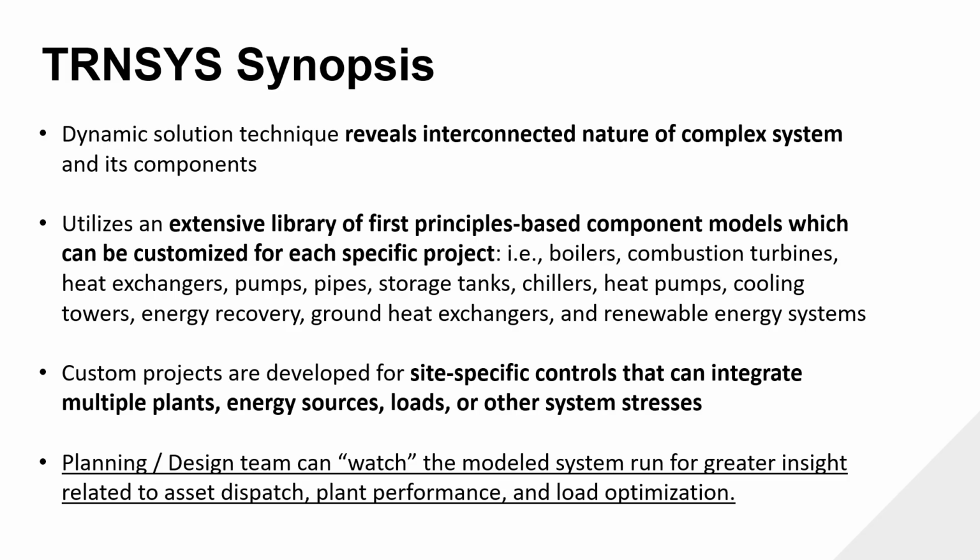For instance, we've got a project in Wisconsin that is a very large geothermal system, one of the largest in North America, and they wanted to put in thousands more boreholes, and they didn't know when they needed this. They're going to add 40 more buildings to their campus. So we built the digital twin, plugged in all their data from the last 10 years, tuned it to that data, and then optimized and looked at, okay, if you change this or add this building here, you're going to need another 500 boreholes 5 years from now as your temperature creep starts to happen. So it's great for predicting future events.